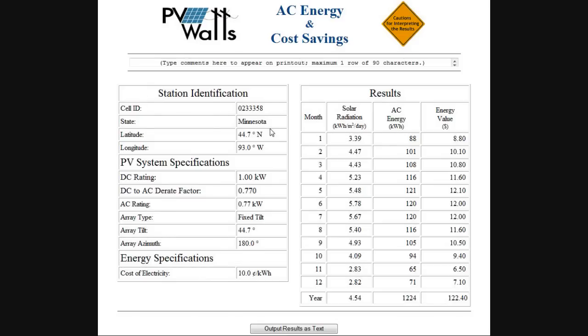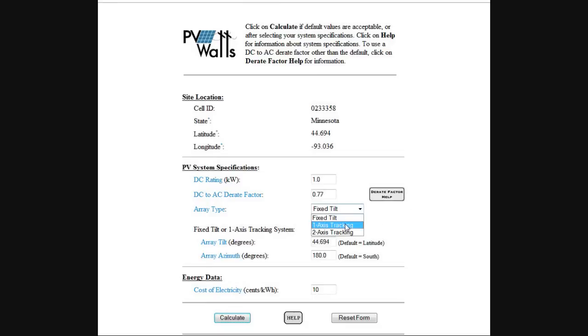After hitting calculate, it generates a result. Based on different months, it calculates kilowatt hours per square meter per day and how much AC energy in kilowatt hours the system will produce. In Minnesota, you can see that in the worst month — December — a 1 kilowatt fixed panel system, properly oriented, would only generate 71 kilowatt hours. But in the best months in the bulk of the summer, it would be up in the 120 range. On average for the whole year, it comes out to 1,224 kilowatt hours.